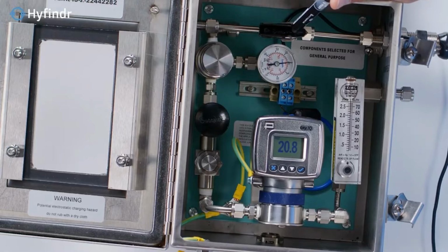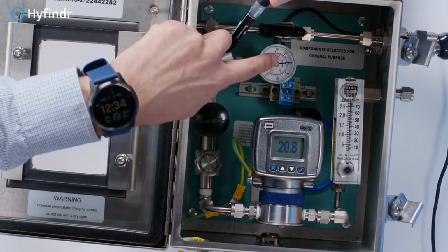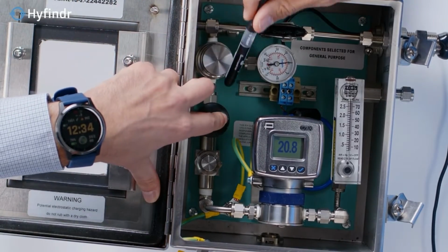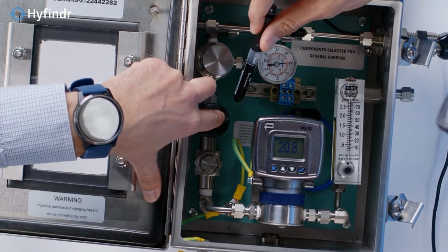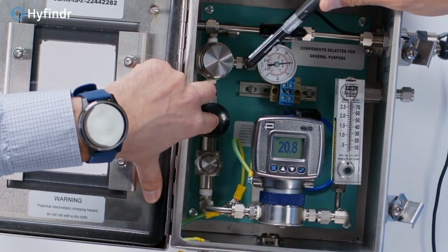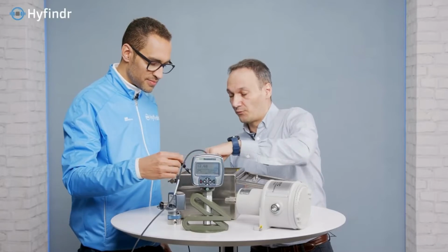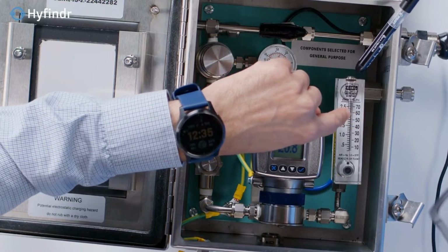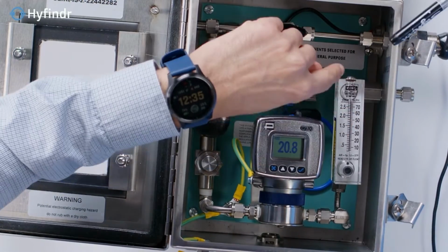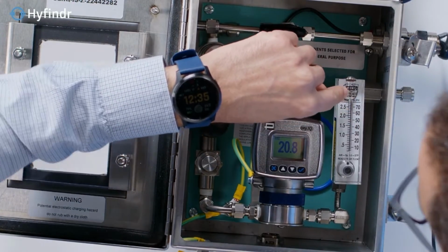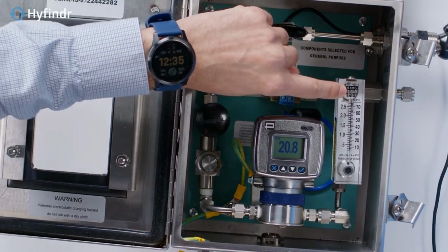And then after, we open and adjust the pressure here. That's the second door we need to open, so to say. That's the needle valve. When we open this needle valve, we look at the flow meter, that the flow rate is about 30 liters per hour. This is standard liters per hour, and this is standard cubic feet per hour.